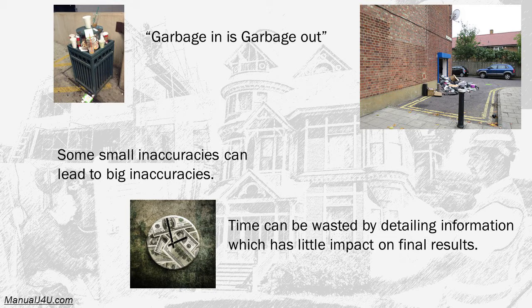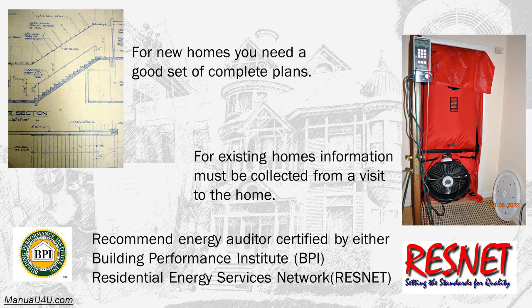For example, air infiltration is often incorrectly estimated, which can lead to large inaccuracy in the load estimate. On the other hand, spending much time trying to get a detailed evaluation of internal loads is not necessary. Small electrical loads have little impact on equipment size, and usage is so variable based on individual tastes that no estimate will be completely accurate.